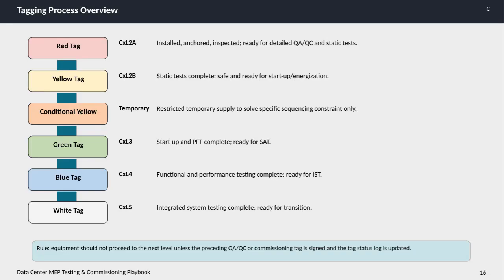Let's walk through the tagging process overview as outlined in the data center MEP testing and commissioning playbook. This process uses a series of color-coded tags to track equipment status through different testing and commissioning phases. We start with the red tag at CxL2A, which indicates that equipment has been installed, anchored, and inspected. At this stage, the equipment is ready for detailed quality assurance, quality control, and static tests. Next is the yellow tag, labeled CxL2B. This tag shows that static tests are complete, and the equipment is confirmed safe and ready for startup or energization. There's also a conditional yellow tag, which is temporary and allows for a restricted temporary supply, specifically to resolve sequencing constraints.